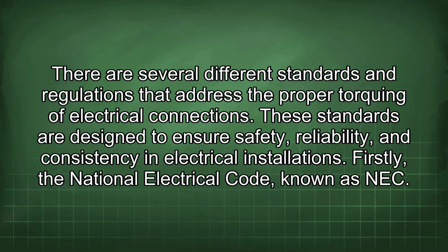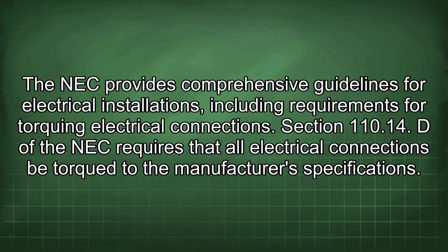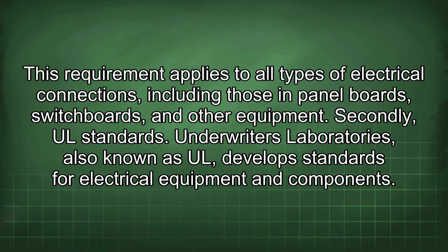There are several different standards and regulations that address the proper torquing of electrical connections. These standards are designed to ensure safety, reliability, and consistency in electrical installations. Firstly, the National Electrical Code, known as NEC. The NEC provides comprehensive guidelines for electrical installations, including requirements for torquing electrical connections. Section 110.14(D) of the NEC requires that all electrical connections be torqued to the manufacturer's specifications. This requirement applies to all types of electrical connections, including those in panel boards, switchboards, and other equipment.